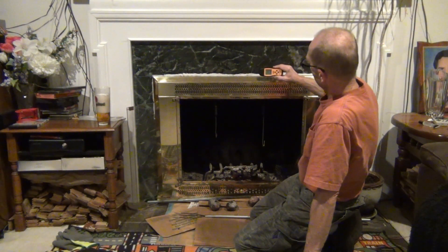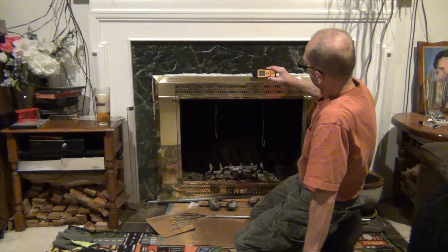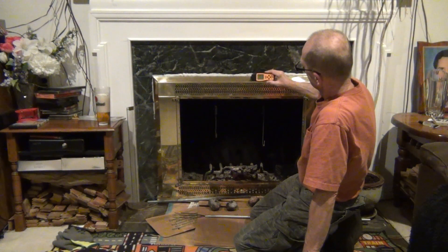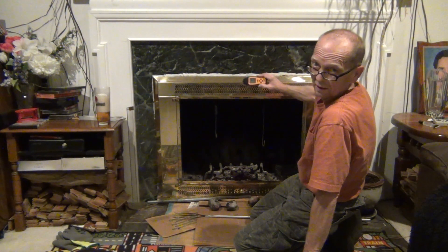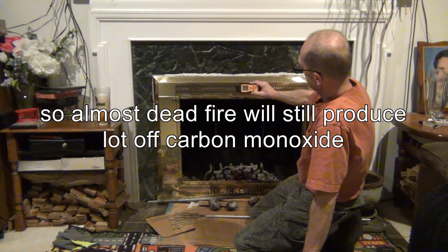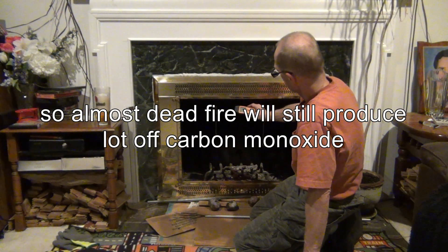We've already got 20 ppm and you can see how fast it's reacting — it starts beeping right away. Now it's coming up to 50 ppm and staying around 50 to 53. It's up to 60 now, and if I go inside it's going to go up even more of course.